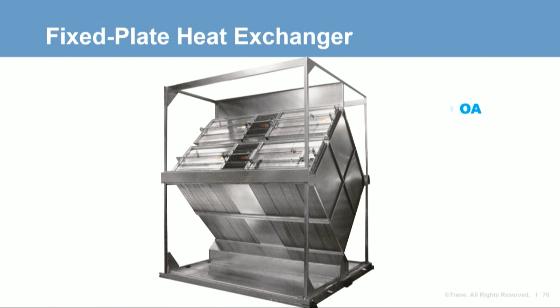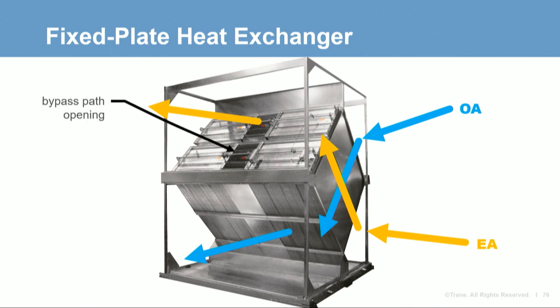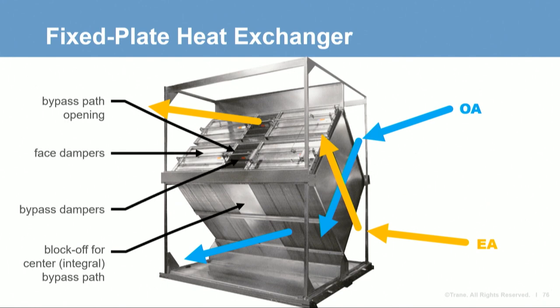Here's a photo of a plate exchanger where airflows are cross-flow, with outdoor air entering the top back side and passing down through the heat exchanger, while exhaust air enters the bottom back side and travels at an upward angle. Plate exchangers can be constructed with a bypass path through the middle of the heat exchanger. With bypass dampers open and face dampers shut, all the exhaust air passes through this open section in the center — so no heat is transferred.